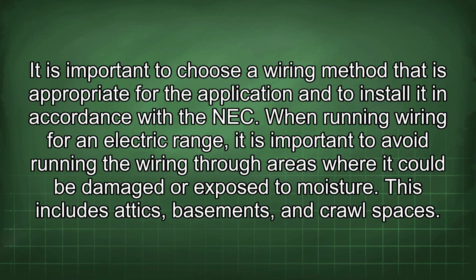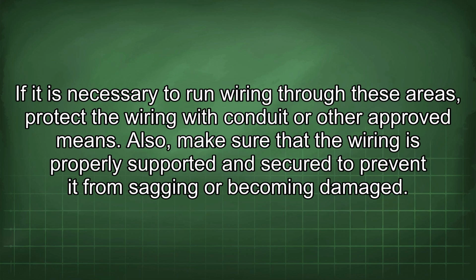It is important to choose a wiring method that is appropriate for the application and to install it in accordance with the NEC. When running wiring for an electric range, it is important to avoid running the wiring through areas where it could be damaged or exposed to moisture. This includes attics, basements, and crawl spaces. If it is necessary to run wiring through these areas, protect the wiring with conduit or other approved means. Also, make sure that the wiring is properly supported and secured to prevent it from sagging or becoming damaged.